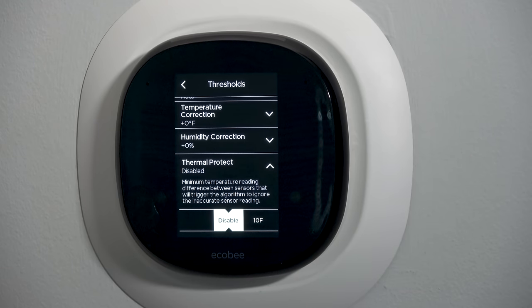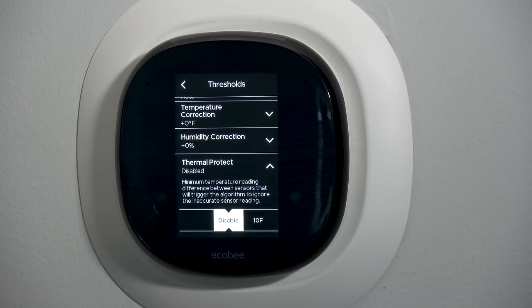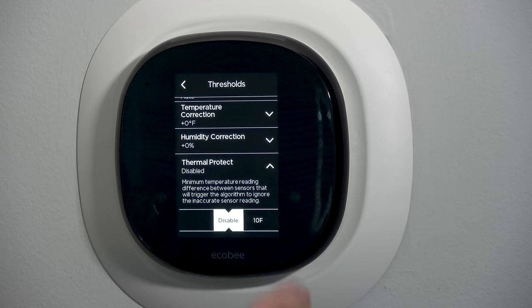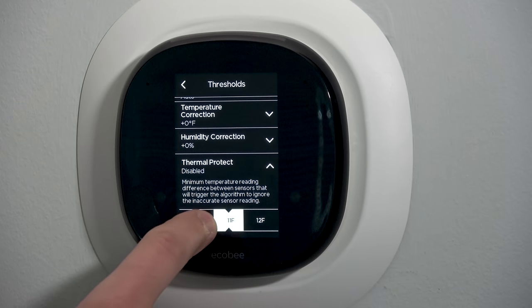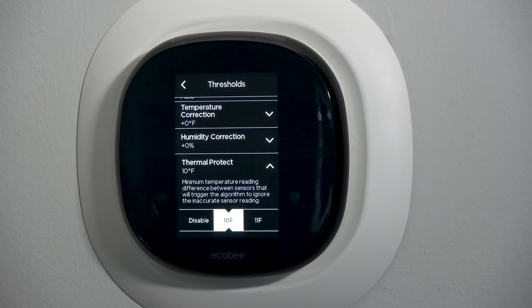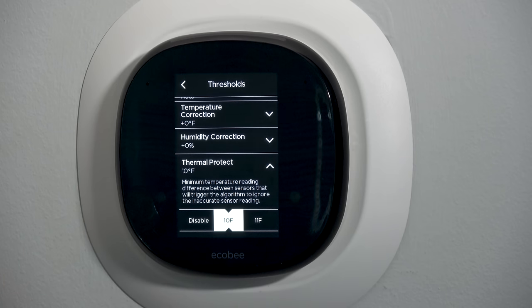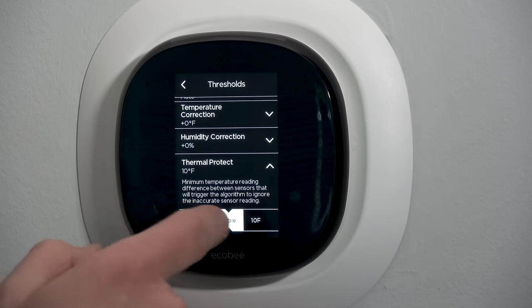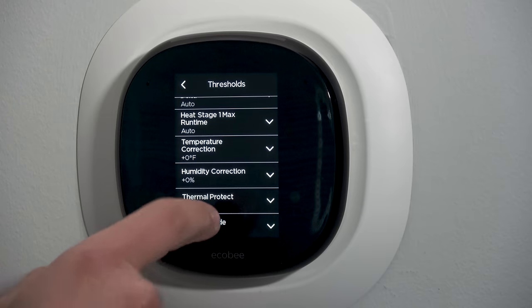Thermal protection: the minimum temperature reading difference between sensors that would trigger an algorithm to ignore an inaccurate sensor reading. If I have multiple sensors and they differ by a certain number of degrees — say 10 degrees — the system determines one of them is bad. This works best with more than two sensors: if you've got three sensors and two are fairly close but the third is way out in left field, it's probably a bad sensor or bad battery. Thermal protection would flag and ignore that sensor.